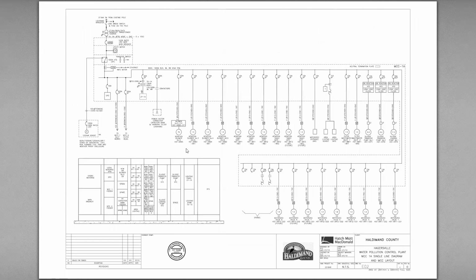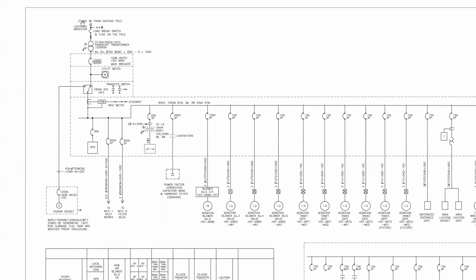This is the single line drawing for the upgrade at the Water Pollution Control Plant. Single line drawing is the main power coming in and how it gets distributed out to the different buildings. So you can see here, we've got a 27.6 kV 3-phase transformer comes in from the pole. There's a lightning arrestor, which is protection from lightning. And there's a load break switch on it. If you've ever seen a giant throw switch from some evil villain's lair mounted to the side of an electrical pole, that's what these throw switches are.